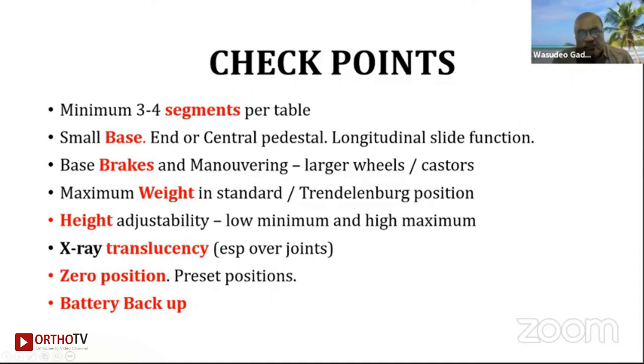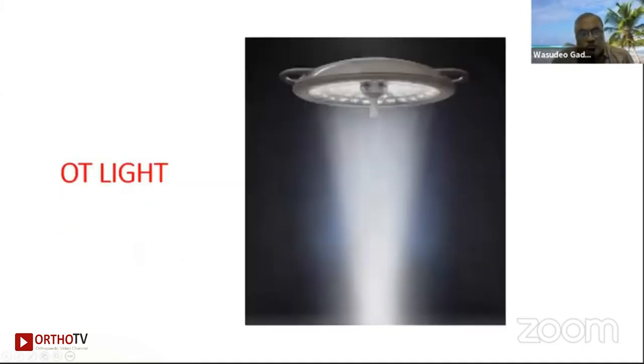Other checkpoints include: small base end or central pedestal, longitudinal slide function, base brakes, maneuvering, larger wheels and casters, maximum weight capacity in standard Trendelenburg position, height adjustability with low minimum and high maximum, X-ray transparency, zero position, preset position memory, and battery backup if it is hydraulic or electric — though it should also be manageable by manual operation.